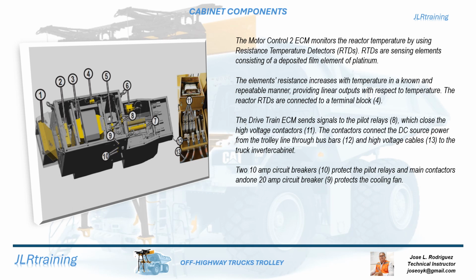The drivetrain ECM sends signals to the pilot relays, 8, which close the high voltage contactors, 11. The contactors connect the DC source power from the trolley line through bus bars, 12, and high voltage cables, 13, to the truck inverter cabinet. Two 10-amp circuit breakers, 10, protect the pilot relays and main contactors. A 20-amp circuit breaker, 9, protects the cooling fan.